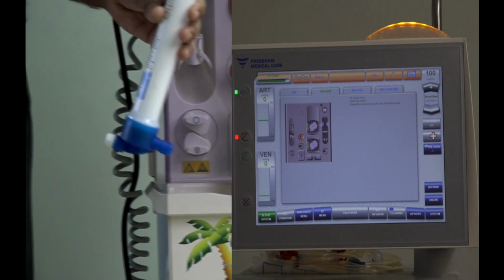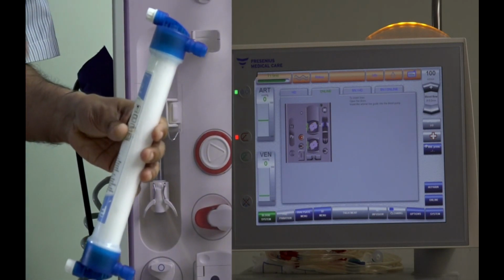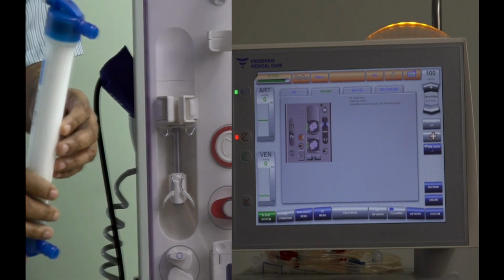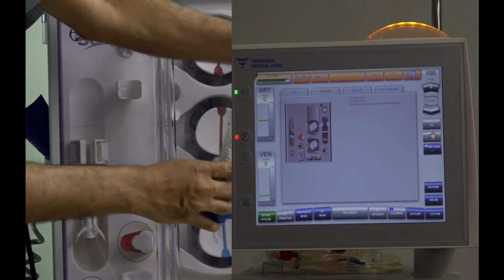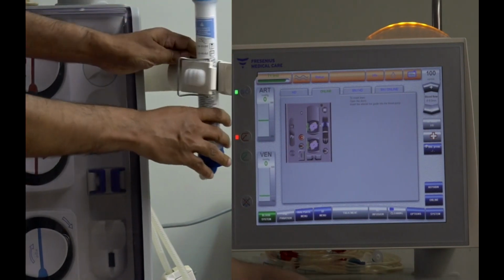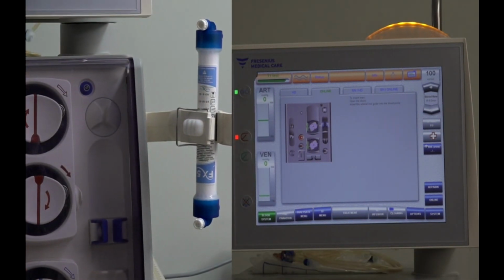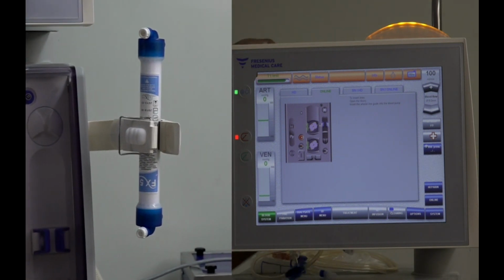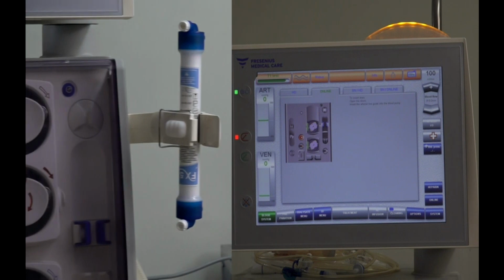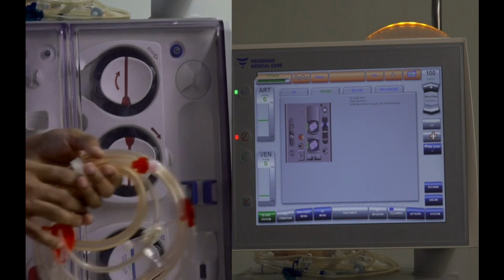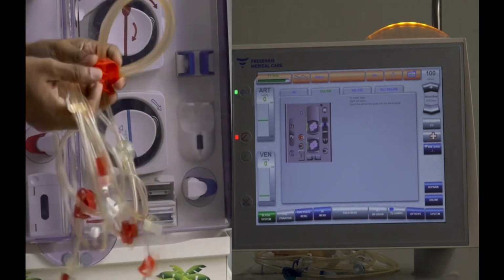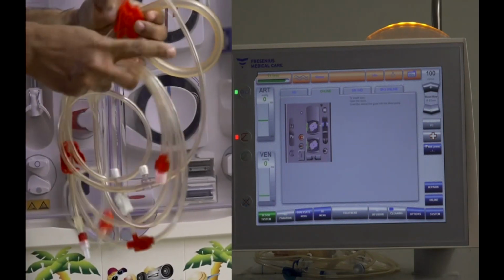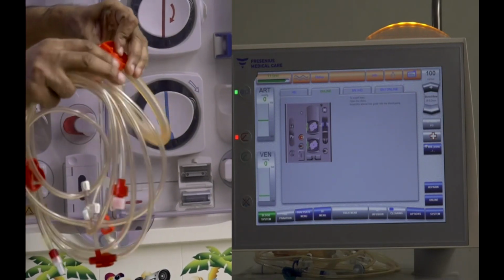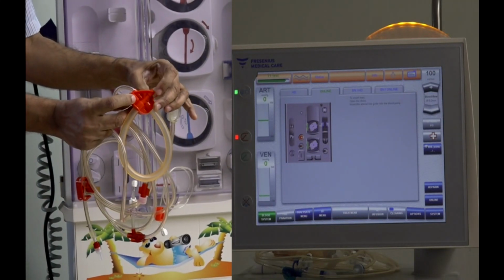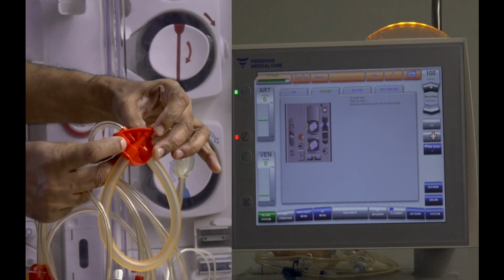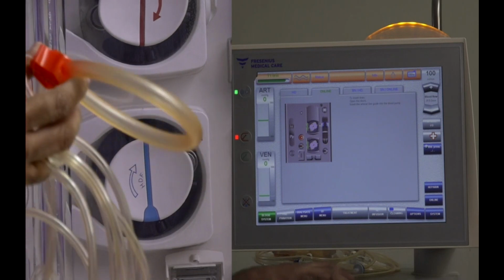The machine with its screen will guide us through the entire process of loading all the lines which are required for this treatment. I'm going to start with the dialyzer. So I will place the dialyzer here on its holder, and now the machine is asking me to load the arterial line. The arterial line is slightly different from the conventional arterial lines. Among other things, it has the pump segment which has a diameter of 8 millimeters as opposed to the normal lines which have 6.4 millimeters, and this portion of the pump segment has a little spike which engages with a sensor on the machine. So let's do that.